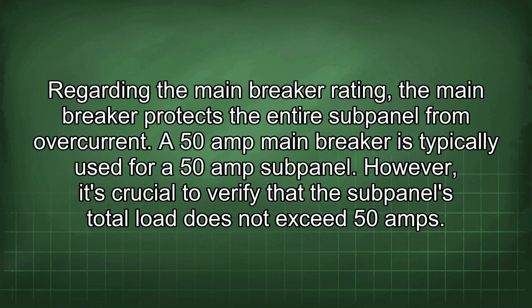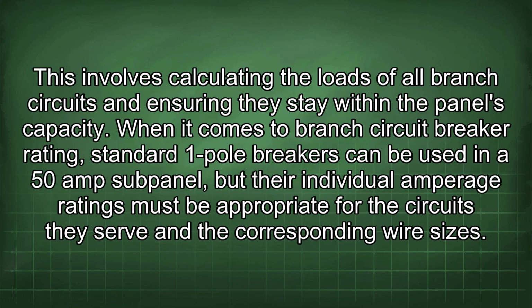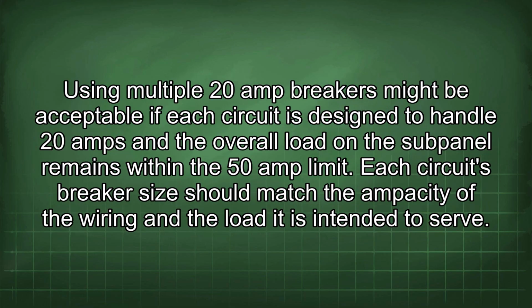Regarding the main breaker rating, the main breaker protects the entire subpanel from overcurrent. A 50-amp main breaker is typically used for a 50-amp subpanel. However, it's crucial to verify that the subpanel's total load does not exceed 50 amps. This involves calculating the loads of all branch circuits and ensuring they stay within the panel's capacity. When it comes to branch circuit breaker rating, standard 1-pole breakers can be used in a 50-amp subpanel, but their individual amperage ratings must be appropriate for the circuits they serve and the corresponding wire sizes. Using multiple 20-amp breakers might be acceptable if each circuit is designed to handle 20 amps and the overall load on the subpanel remains within the 50-amp limit.